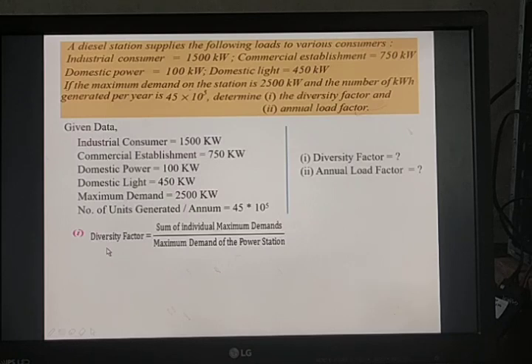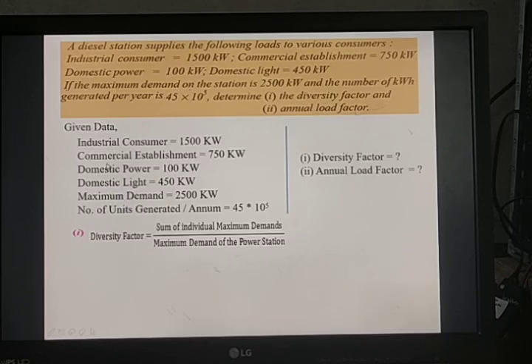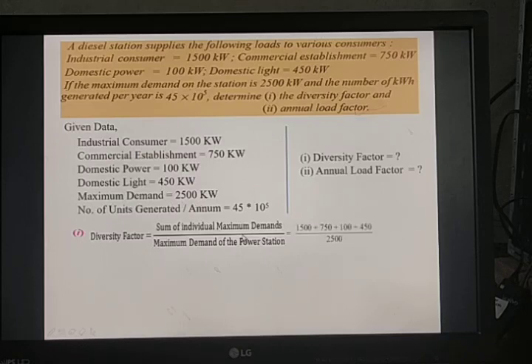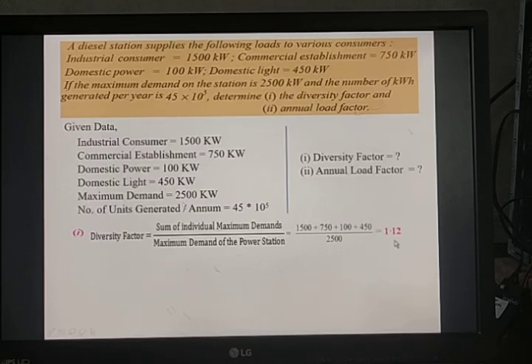The diversity factor is defined as the sum of individual maximum demands divided by the maximum demand on the power station. Substituting: (1,500 + 750 + 100 + 450) / 2,500 = 2,800 / 2,500 = 1.12. As expected, the diversity factor is always greater than 1.